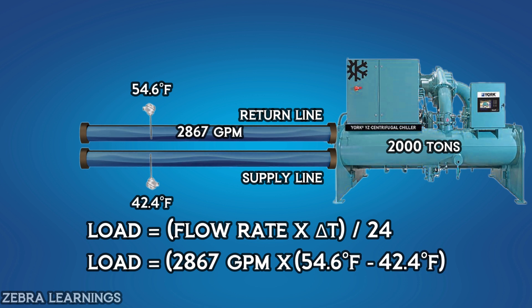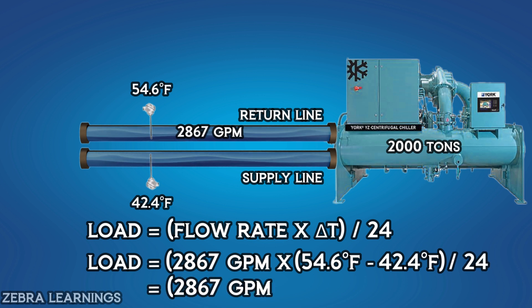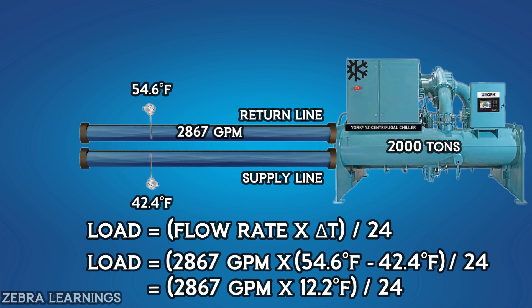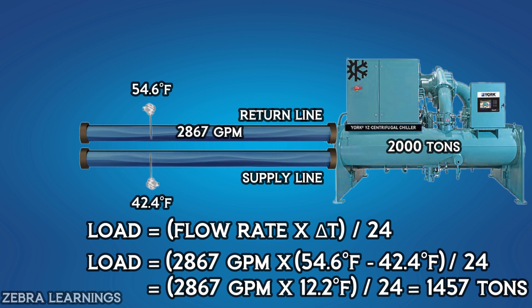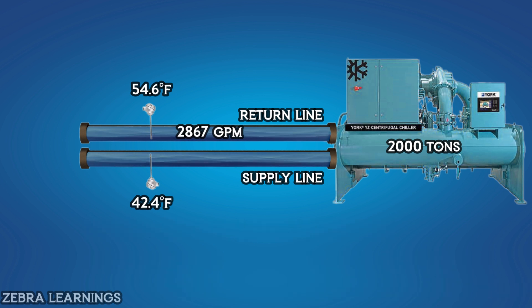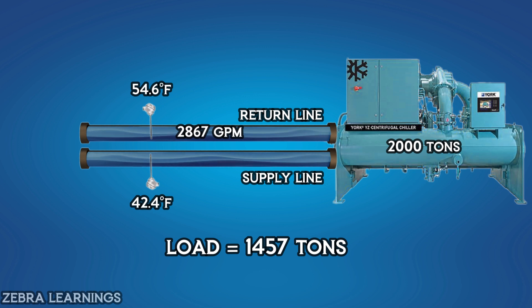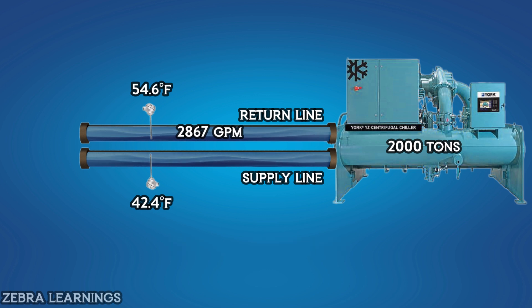Load equals 2,867 gallons per minute multiplied by (54.6°F minus 42.4°F), divided by 24, which equals 2,867 multiplied by 12.2, divided by 24, which equals 1,457 tons. The 2,000-ton chiller is currently running at 1,457 tons load, meaning it is removing heat equivalent to 1,457 tons from the water. This is the chiller load calculation method.